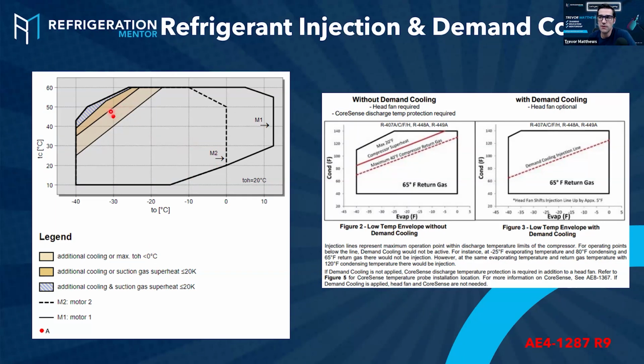But look, I'm running up here. And if you're running up here or even up here, which is even worse, because as we move down, we drop that suction temperature, we drop that suction pressure. That means we got what? Less what? We got less mass flow. So we got less of that nice cool gas coming back. Even though it's minus 40, we just don't have enough coming back. So that's why we have additional cooling, or suction gas superheat, additional cooling and specific suction gas superheat. So less than 20K, which is 36 degrees Fahrenheit. It doesn't matter the units, you just want to understand that.